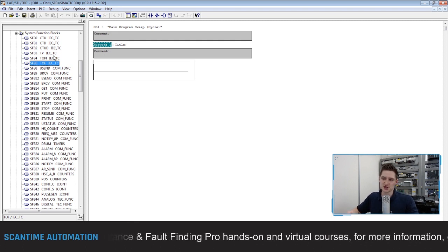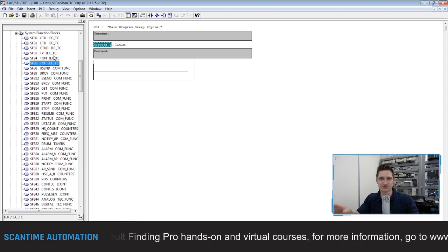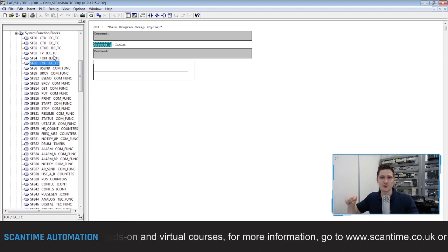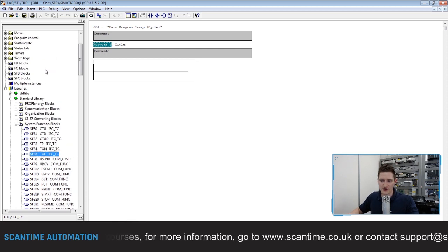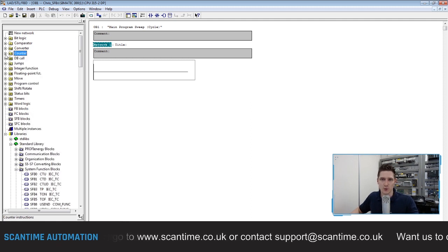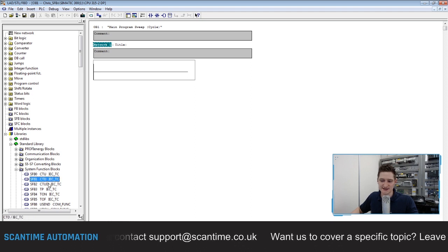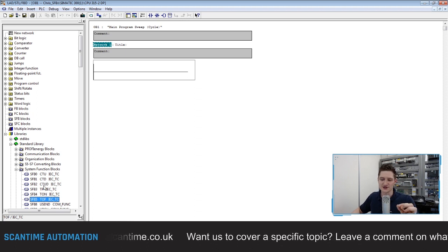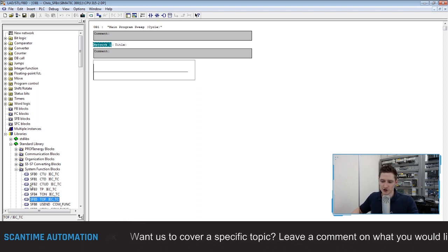What this means is we can create these blocks inside of Siemens STEP7 Professional, and we can then convert that program to another PLC, and it will convert over with those timers as they are designed to the IEC standard. The other counters and timers that Siemens use in these folders, if we use those inside of our programs and try to convert that to another PLC program, wouldn't convert correctly because those timers and counters might not be available in another programmer. However, these CTU, CTD and CTUD and TP, TON and TOF blocks are. These are IEC blocks. And these are the blocks that we're going to have a look at.